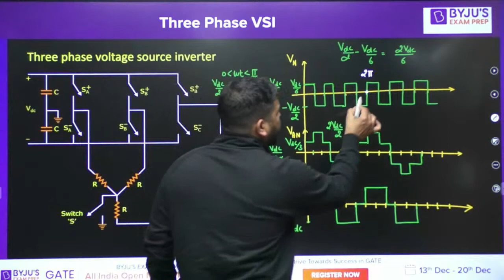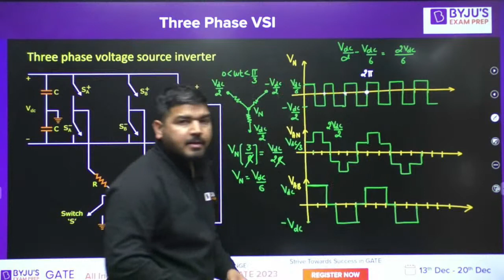It contains triplen harmonics. Now look at the neutral point voltage. In the neutral point voltage, up to this point there are 3 cycles. It means if the switch is not grounded, this neutral point voltage will always contain triplen harmonics only. Vn contains triplen harmonics only.